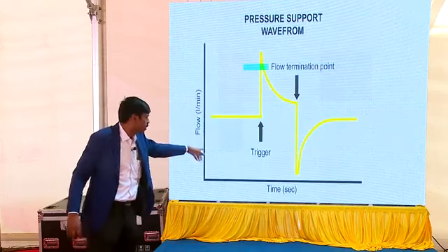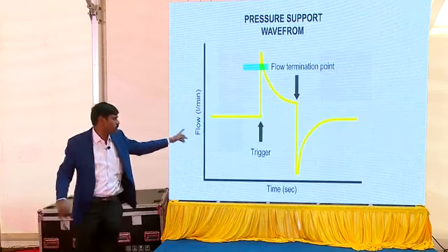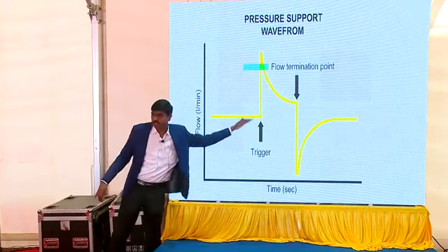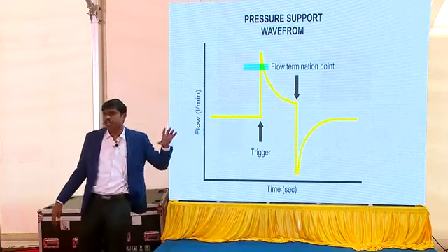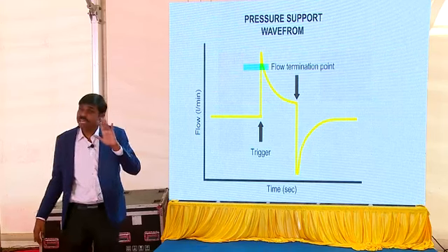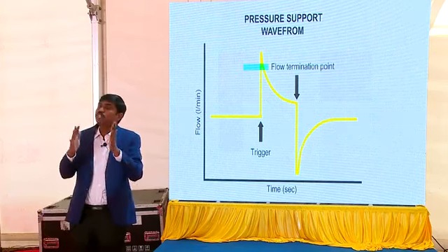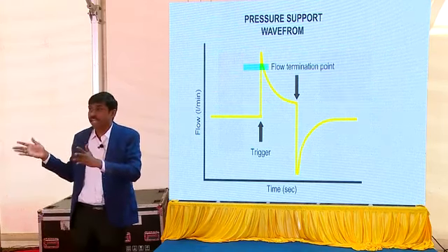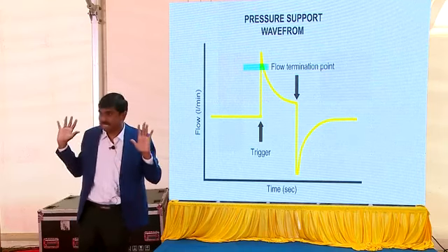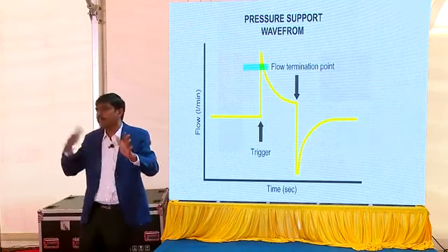Yeah, this is PSV. Here you see the movement from inspiration to expiration. The bottom one is expiration. Now in normal SIMV and SIPPV, the change from inspiration to expiration is called cycling. Cycling is basically time based, so after 0.3 seconds it moves.